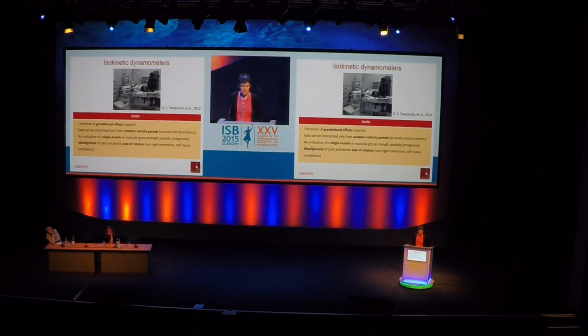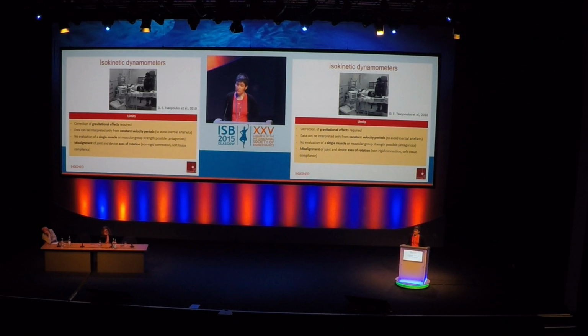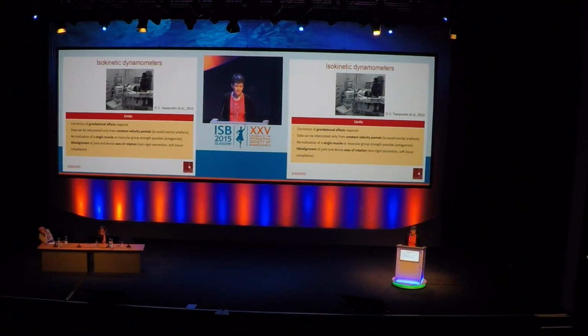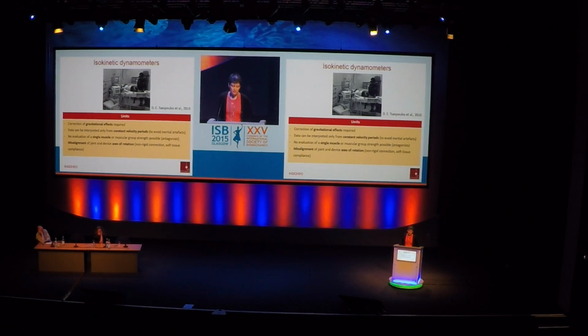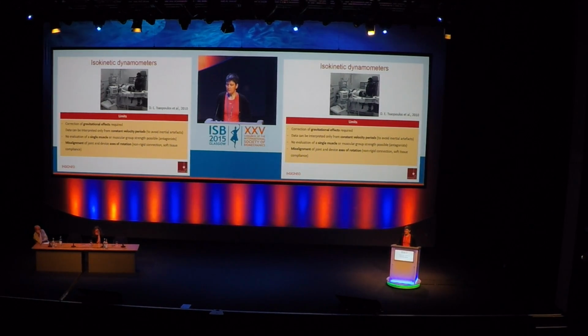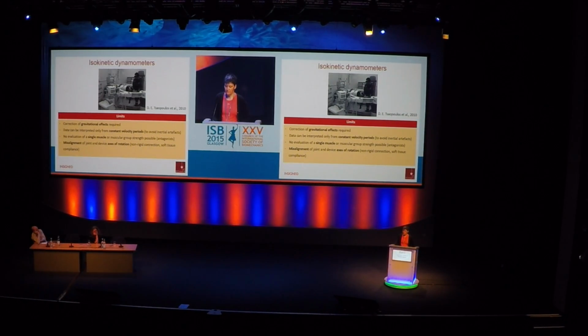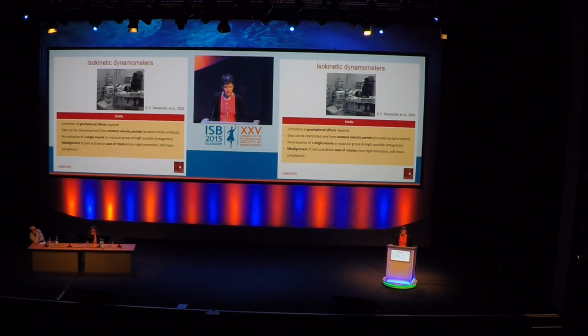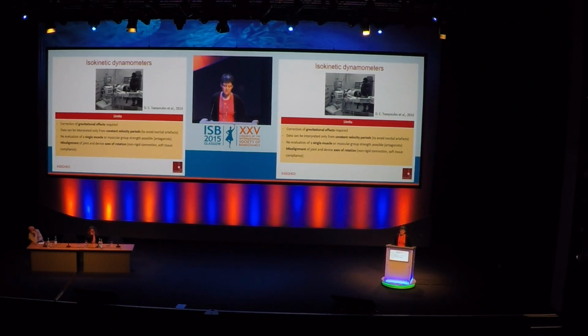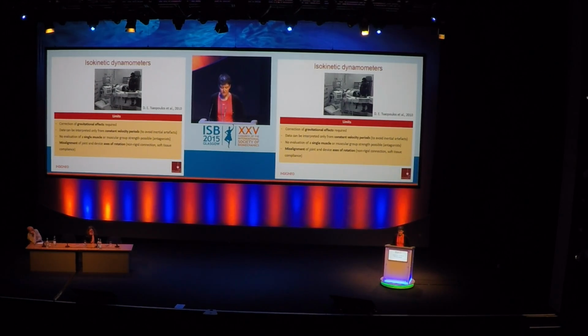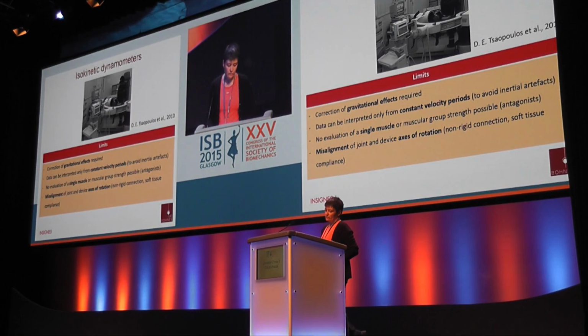The limits are that you need to correct gravitational effects with this kind of device. You can only interpret the constant velocity period because of inertial artifacts, and you cannot evaluate a single muscle because of antagonist muscle activity. Moreover, artifacts can appear due to a misalignment of the joint and the device axis of rotation.